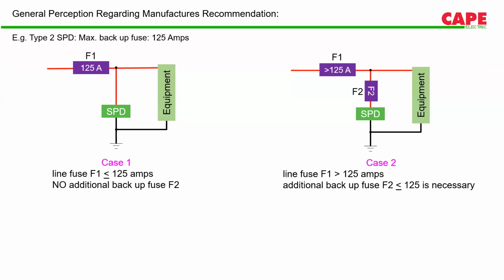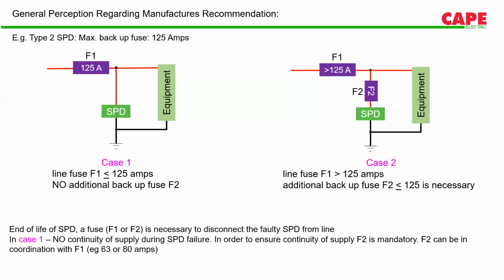So these are the two important things we have to take care of while selecting a backup fuse. First, the backup fuse, or F2, shall not be more than the primary fuse, the primary incomer, which we call F1. And second, F2's rating shall be maximum up to what the manufacturer has claimed. Now, in case one, another thing we see is once this SPD fails with a short circuit, this F1 will trip. Once F1 trips, or the fuse blows off, the supply to the equipment gets disconnected.